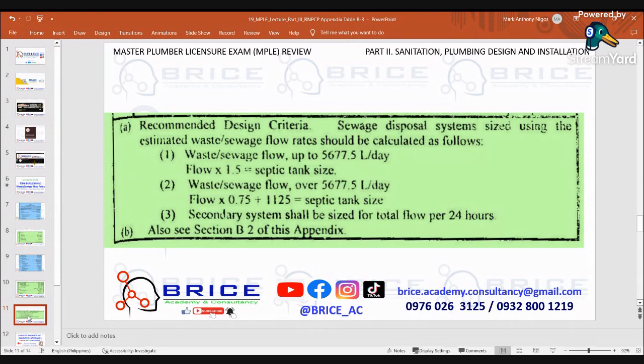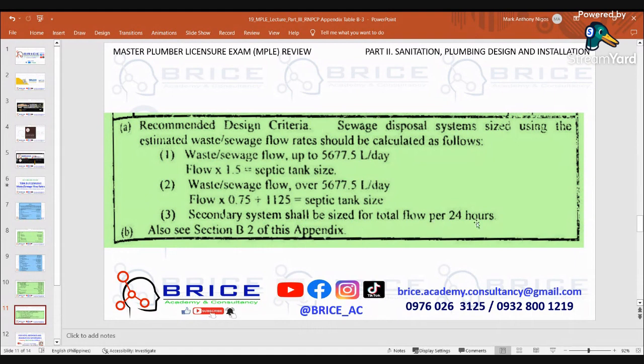Recommended design criteria, letter A — Sewage disposal system size using the estimated waste or sewage flow rate should be calculated as follows: Number 1 — waste or sewage flow up to 5,677.5 liters per day: flow times 1.5 equals septic tank size. Number 2 — flow over 5,677.5 liters per day: flow times 0.75 plus 1,125 equals septic tank size. Number 3 — secondary system shall be sized for total flow for 24 hours.